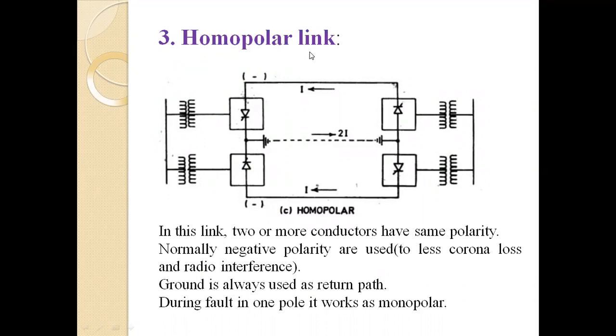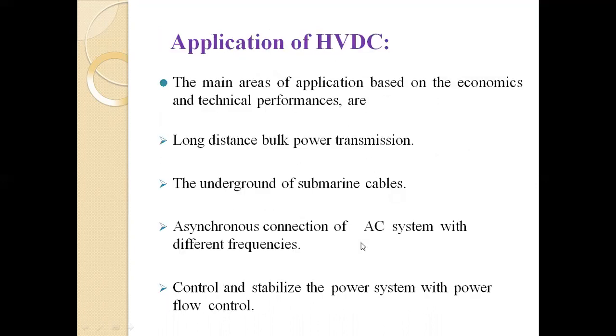The third type of DC link is the homopolar link. Like the bipolar, there is a homopolar link, but here both conductors use a negative converter. The same step-up transformer is connected to the AC source and the step-down is connected to the receiving end, and this converter converts the AC into DC. In this link, two or more conductors have the same polarity. Normally, negative polarity is used for less corona loss and radio interference. So we use negative polarity because it reduces corona loss and also radio interference. Here the ground is always used as a return path. During a fault in one pole, it works as a monopolar link. If a fault occurs in any one conductor, then we can use the second conductor as a monopolar link.